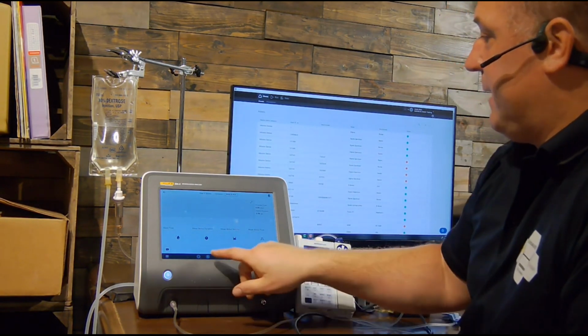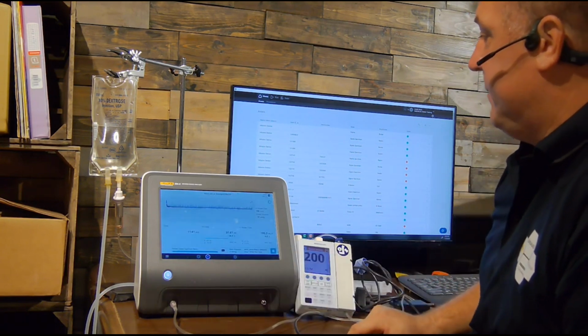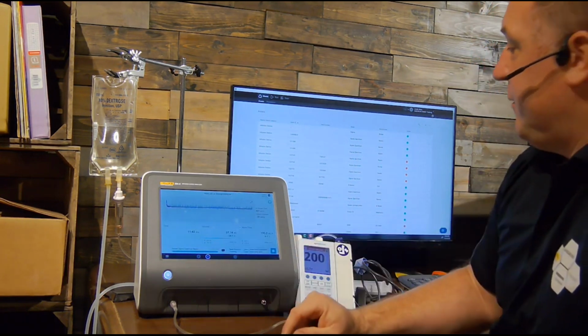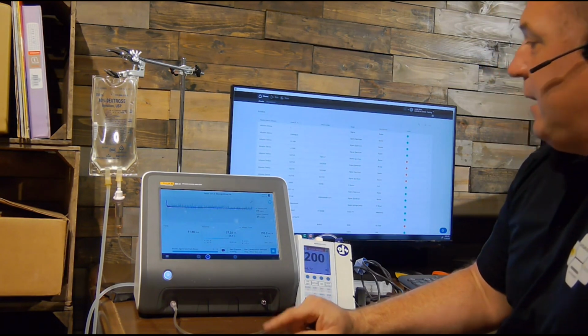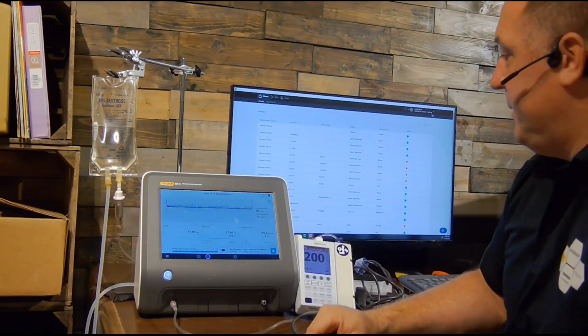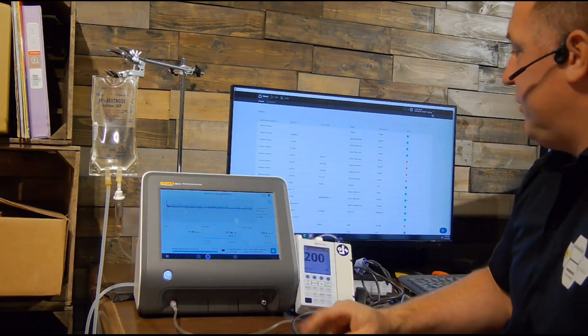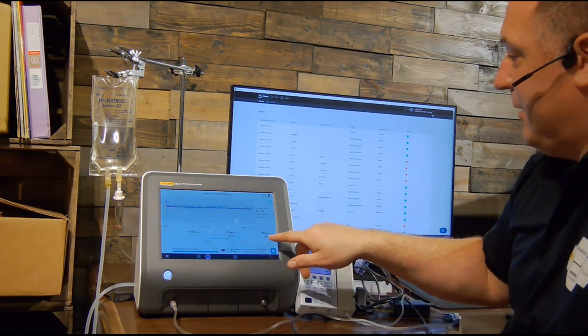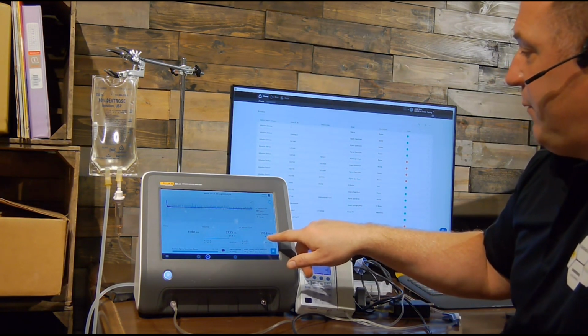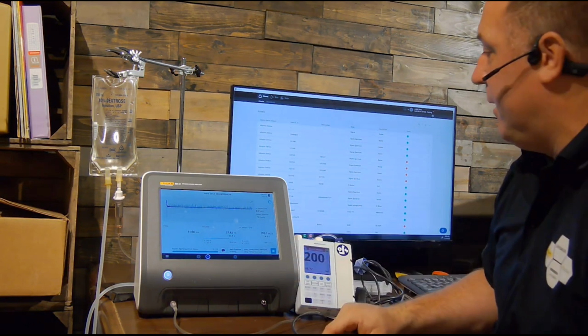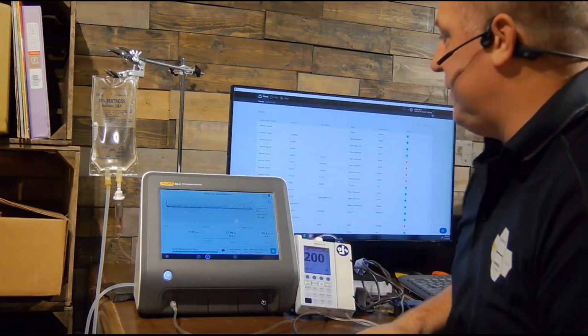All right, let's go back and check back to our pump again here. So we are 11 minutes and 43 seconds into it. We're at 37.32 milliliters, and my mean flow is still around 190. So we're right against that limit at 4.9, and our limit was 5.0. We'll see how this pump finishes out here.